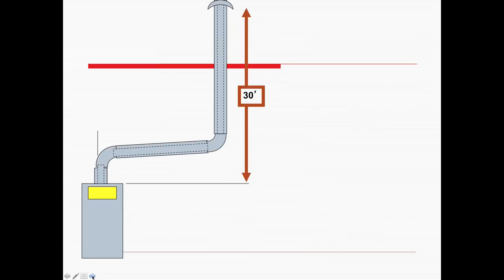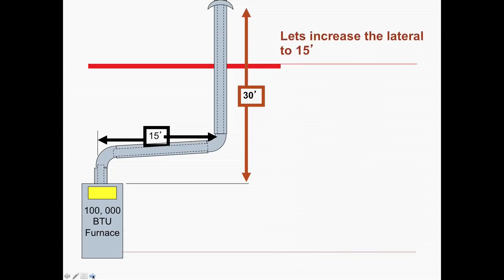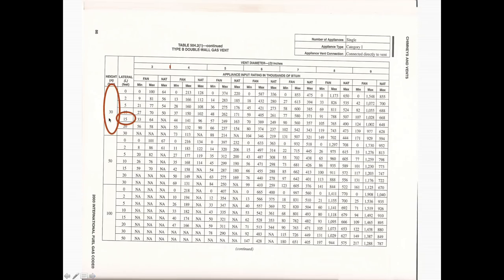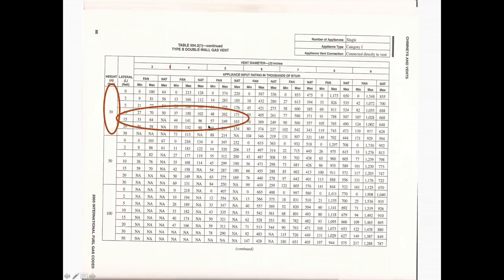Now we have still a 30-foot height but a longer lateral — 15 feet. Same height, same furnace, just a 15-foot lateral. Now here at 30 feet, 15-foot lateral, if you go four-inch you'll only get 96,000 BTUs, so you can't do 100,000 on there. You have to go to the natural column on five-inch, where you can do 163,000 BTUs.